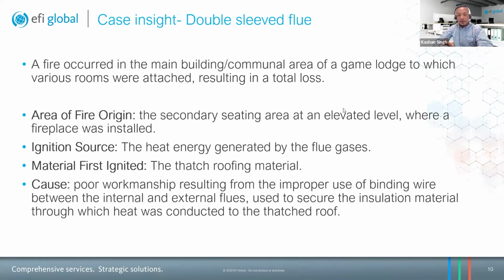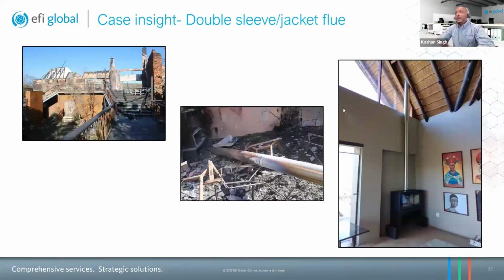Material first ignited was the thatch roofing material, and poor workmanship resulted in the improper use of binding wire between the internal and external flues, used to secure the insulation material through which heat was conducted to the thatch roof. Just a small image of a section of the building. In the center image, we have the double sleeve flue, where you can see clear oxidation and thermal discoloration. The final image on the right-hand side is the original installation where the double sleeve flue penetrated through the thatch roof material. And of course, that's where we identified the fire to occur.